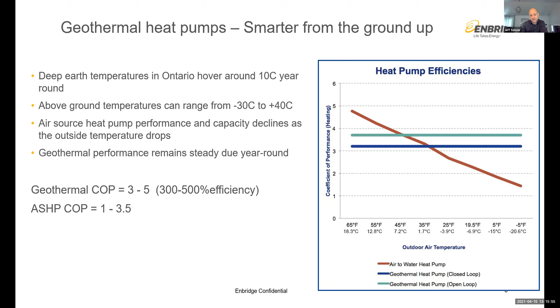So the second part of these systems is the ground heat exchanger. And this is really where the magic happens. We're using the earth as a thermal battery. It provides a heat source in the winter because it's not exposed to the colder elements above ground. And in the summer, it's a large heat sink where we can reject unwanted energy from within the buildings to cool them, disperse that heat into the ground, and potentially recapture it later in the season when we need heating again.